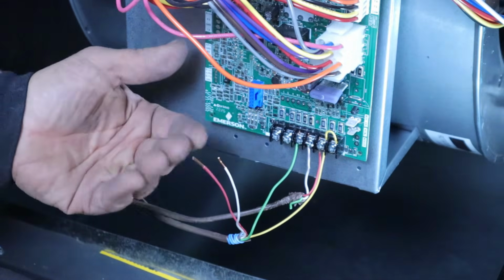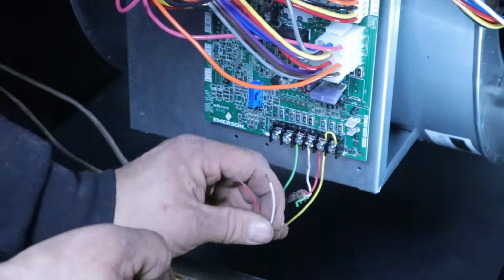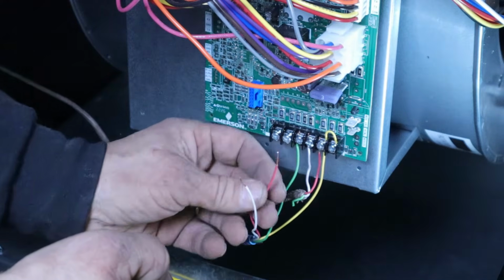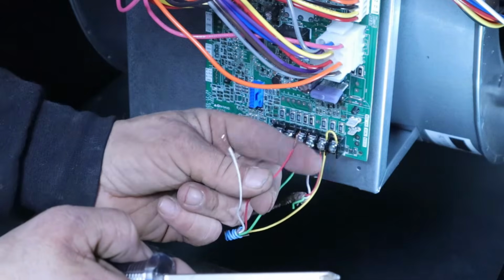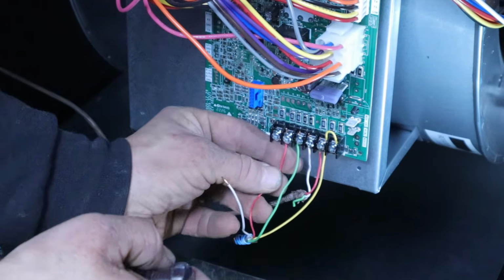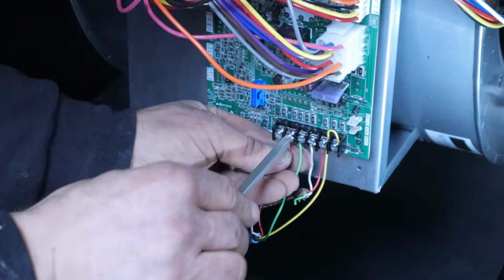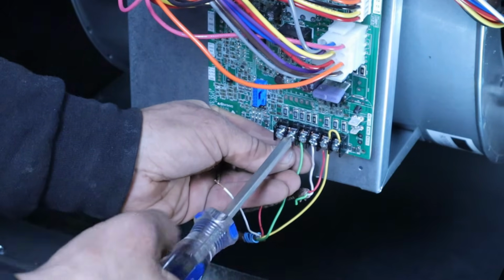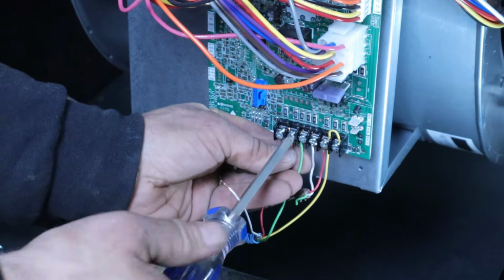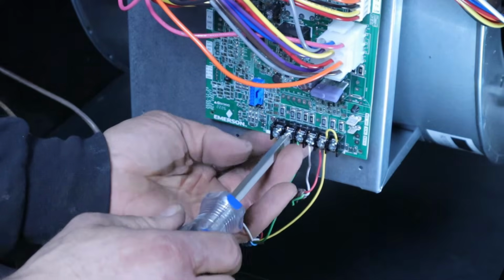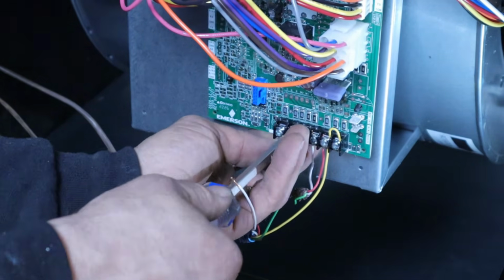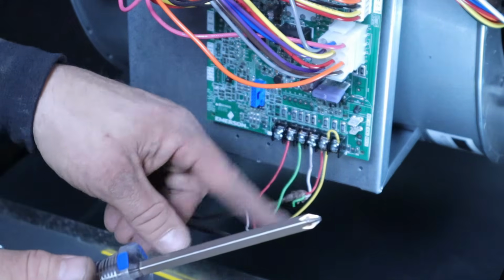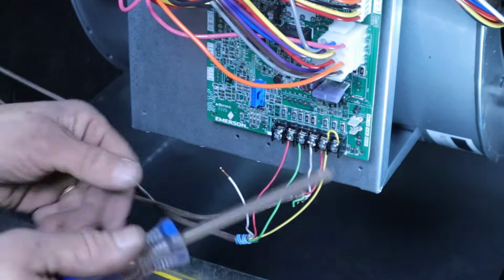The blower will still turn on when it calls for heating or cooling. So I got that hooked up. Now I'm going to hook up to 24 volts. That's the power that sends 24 volts up to your thermostat. And that 24 volts will always be up on the thermostat, waiting for the thermostat to call for heat or cooling. And that 24 volts will be sent to the heating or cooling wires depending on what the thermostat's calling for.